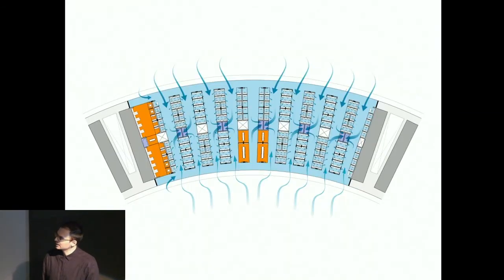Looking in plan, you see this: the chimney is split down the middle, serving opposite cells, let's call them. So you pull in fresh air from both sides. The important thing here is that with wind-driven ventilation, you're normally limited to the plan depth — it can't be too deep. But with buoyancy ventilation, you can get really deep.